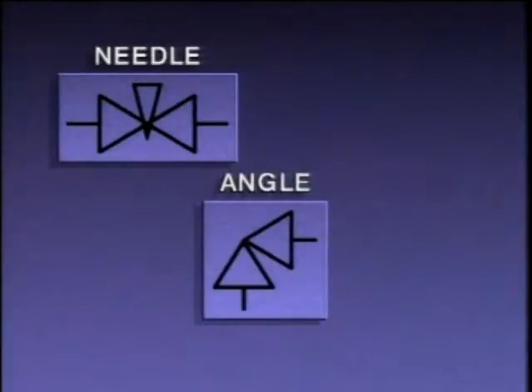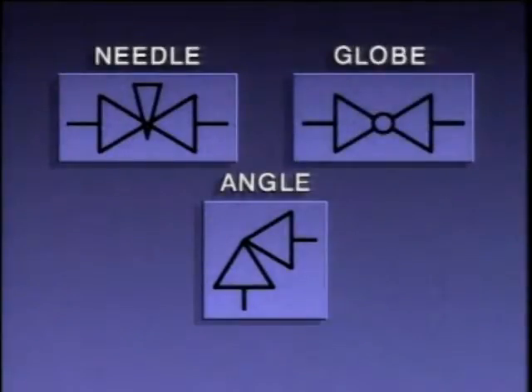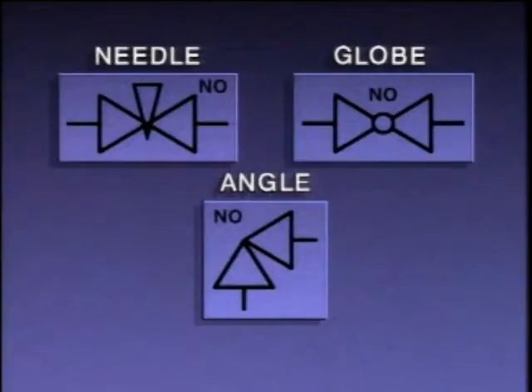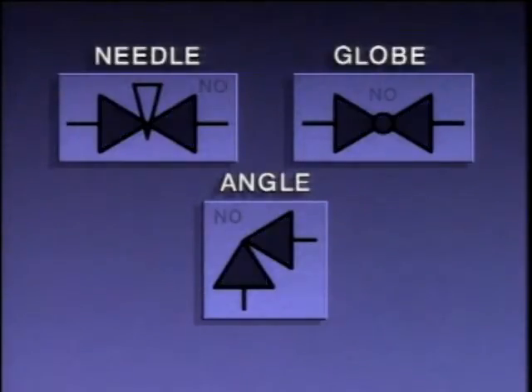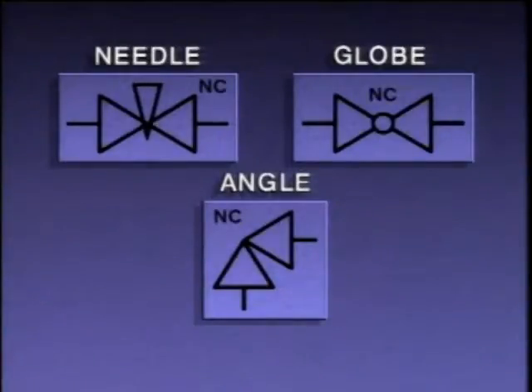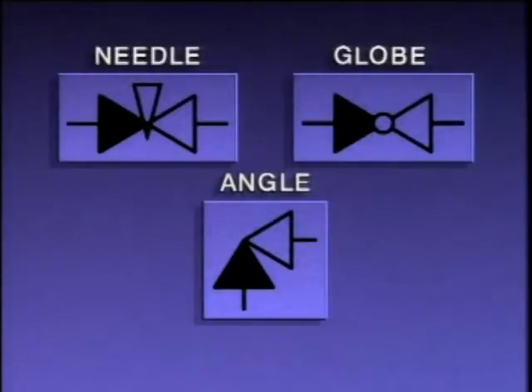An angle valve and a globe valve each have their own symbols on piping diagrams. If the symbols look open or have the letters NO beside them, the valves are normally open. If the symbols are filled in or have the letters NC beside them, the valves are normally closed. The symbol may also be shown partially filled in to indicate the valve is in a throttled position.